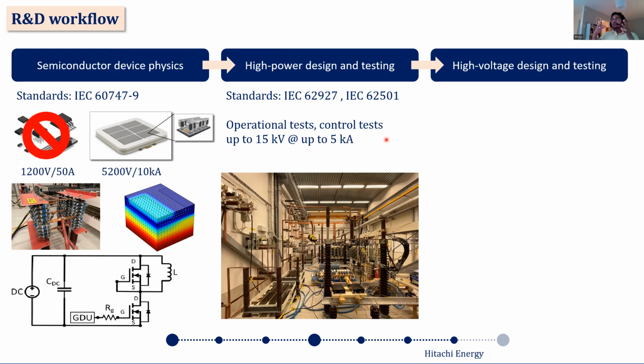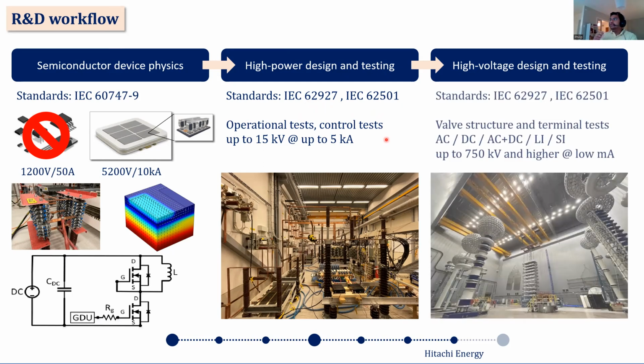And then once we have tested the high power part, so the entire converter topology, we go into the actual high voltage design. So it's the mechanical design of the entire valve that is extremely important because the final HVDC station operates up to maybe 800 kV to 1,000,000 volts. We can't take any sort of failures. I would like to mention that the main dielectric, the primary insulation in HVDC valves, is usually just air. So there's no oil anywhere because of a lot of different factors.